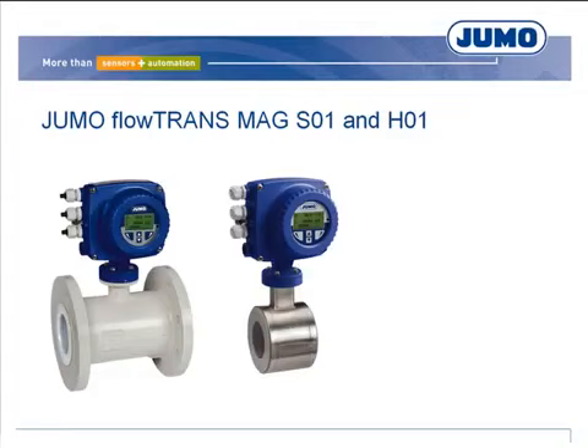The JUMO FlowTrans Mag is a magnetic-inductive flow meter for liquids in industrial and hygienic applications and processes. This unit features maximum accuracy and user-friendliness. The measuring principle is the same as the insertion MID. However, the full pipe cross-section is used for the measurement, whereby an accuracy of up to 0.2% deviation from the measured value is obtained. By the installation of these devices, there is no additional pressure loss in the system, since no interfering contours or constrictions are present in the measuring tube.